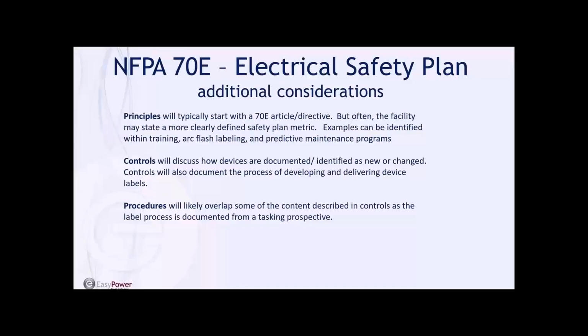Now, many facilities would say, well, if we have new equipment, what's my latitude of actually posting a new arc flash label on that equipment? And many facilities would choose to define that metric, say 6 months or a 1 year period, where labels need to be posted on any revised equipment, and that would be new.